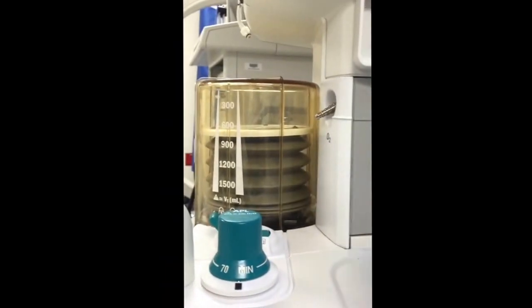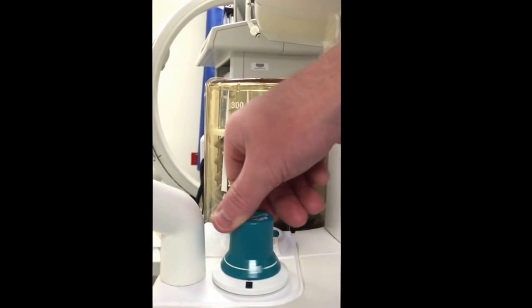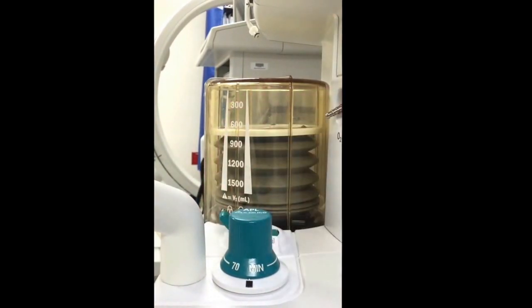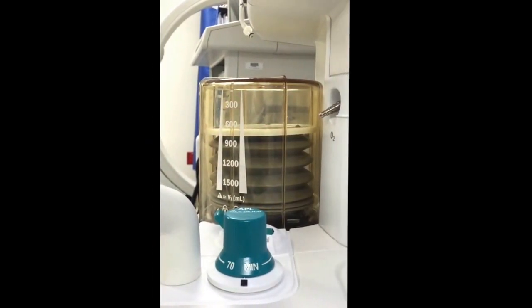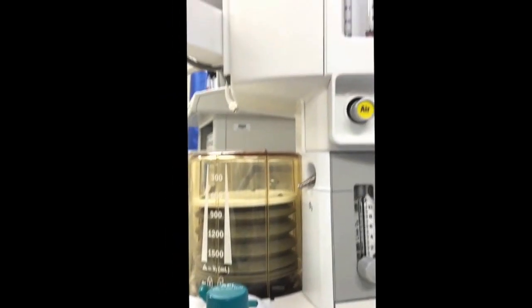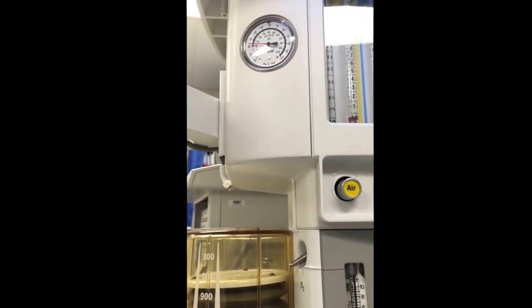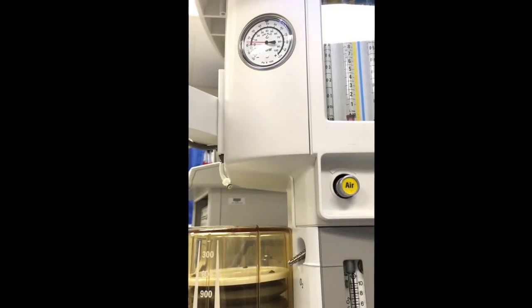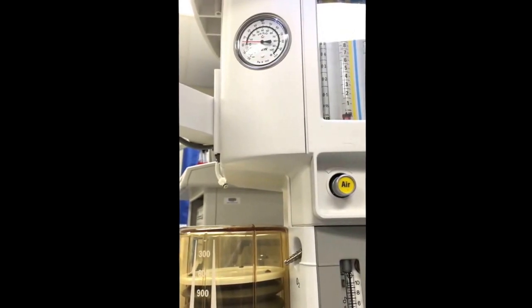Another way to check the scavenging system is to completely open up your APL valve, hold the Y piece on your circuit, and hold the O2 flush, and make sure that your pressure does not go over 10 centimeters water while holding the flush valve.